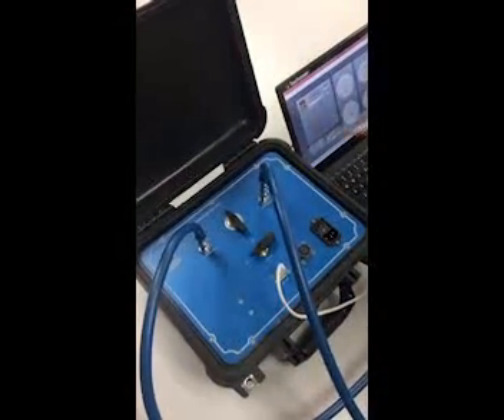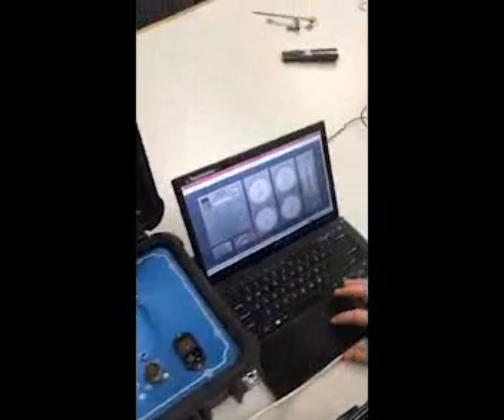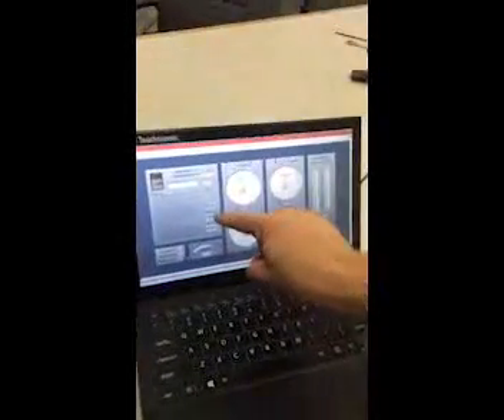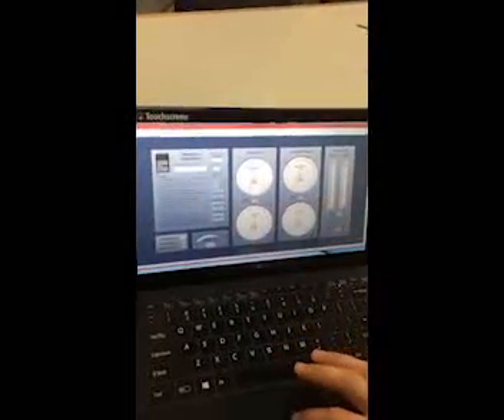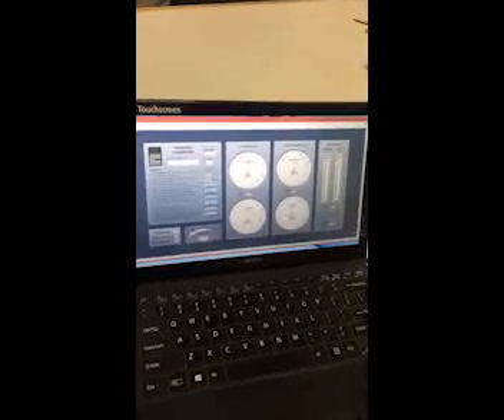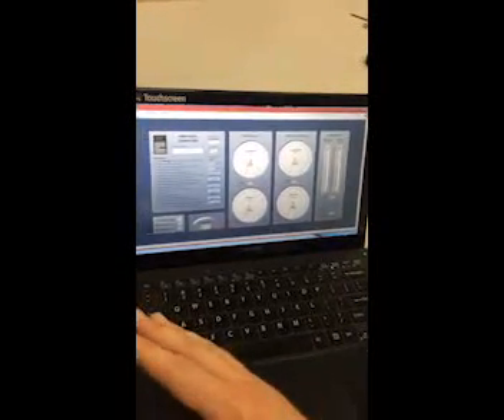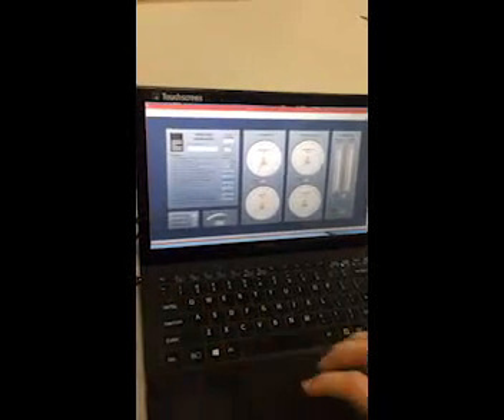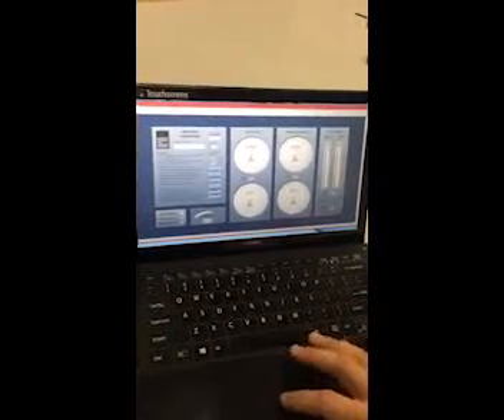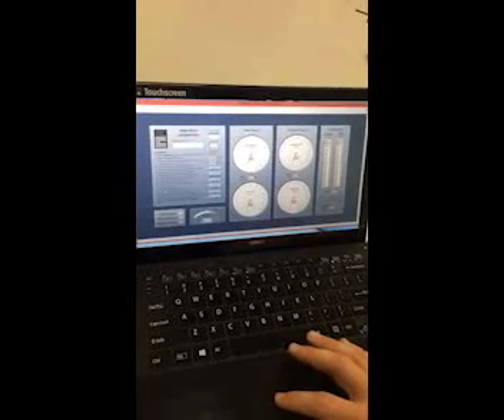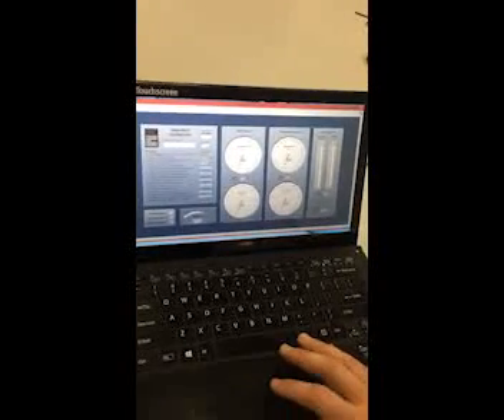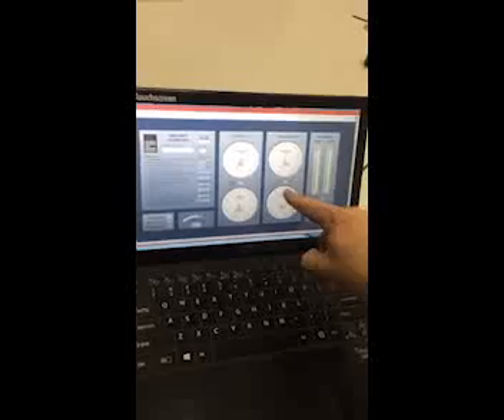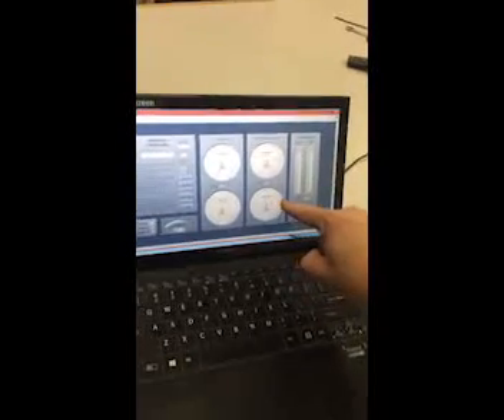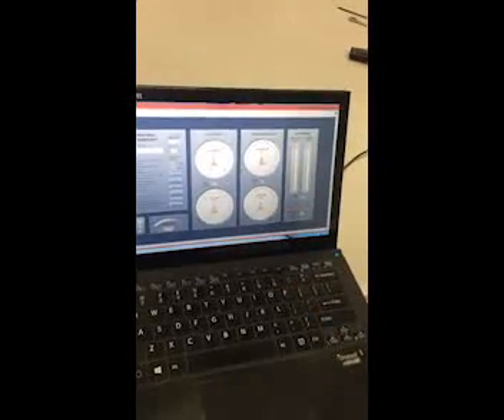Step number 11 on the computer says press 0 dP. What we're doing here is there's your button that says 0 dP. We're going to press this. And again, this is not zeroing the differential pressure transducer inside your FM50. It's actually zeroing the dP inside of the test set. So once we press 0 dP, we go to step number 12 that says verify test set dP reads 0. That's going to be your gauge in the bottom right hand corner. Test set dP, that should read 0.